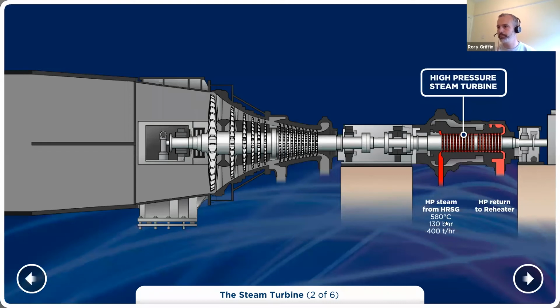So the HP steam comes from the boiler. It's up around 130, 140 bar pressure, more like 560 degrees. And that's actually a little bit high. It's probably closer to 330, 340 tons per hour. When it flows through the HP turbine, it's the same process like you saw in the compressor, where you have a series of blades catching the steam, nozzles straightening them up. You get a flow through, and when it comes out the exhaust of the HP, this is actually called cold reheat. So this is more like IP superheated steam now. It's drop temperature and it's drop pressure.